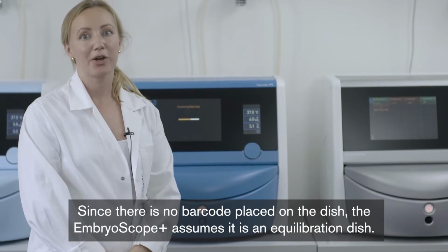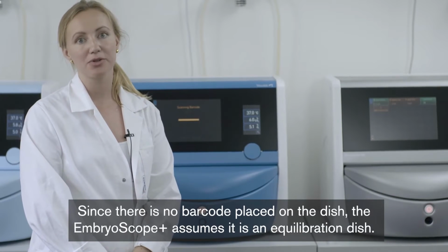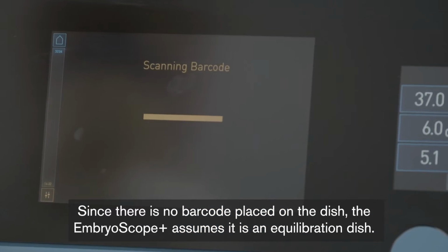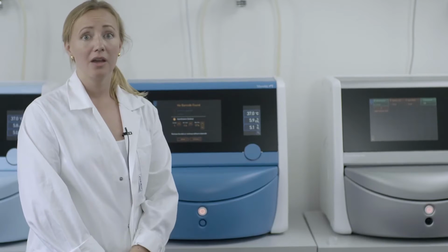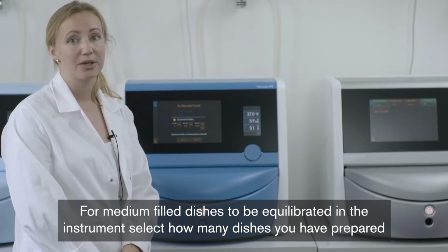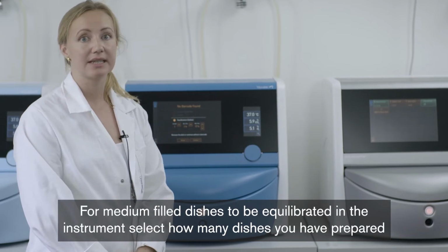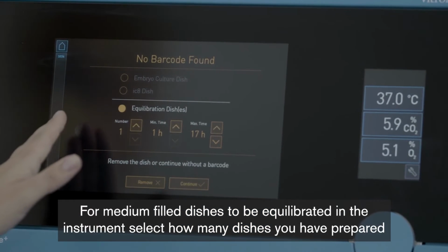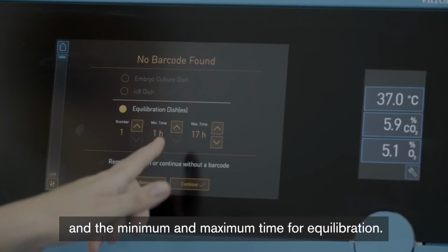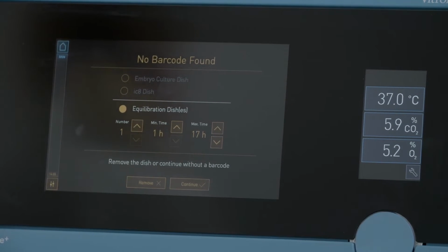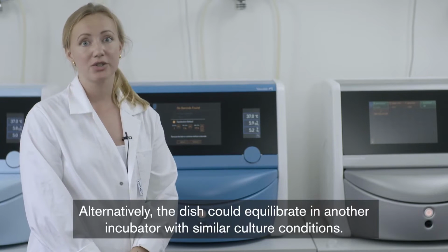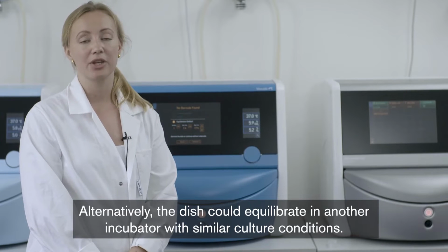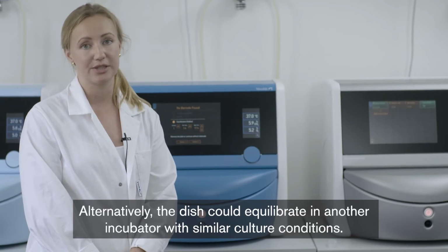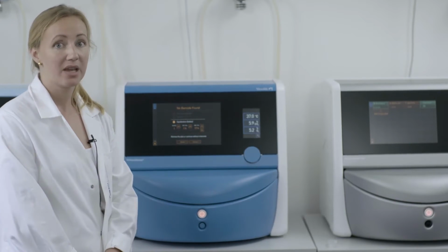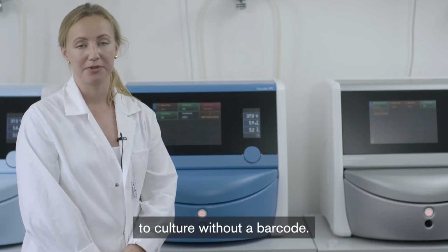Since there is no barcode placed on the dish, the EmbryoScope Plus assumes it is an equilibration dish. For medium-filled dishes to be equilibrated in the instrument, select how many dishes you have prepared and the minimum and maximum time for equilibration. Alternatively, the dish could equilibrate in another incubator with similar culture conditions. Press Continue to culture without a barcode.